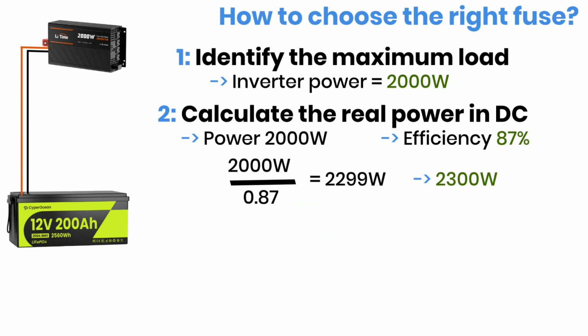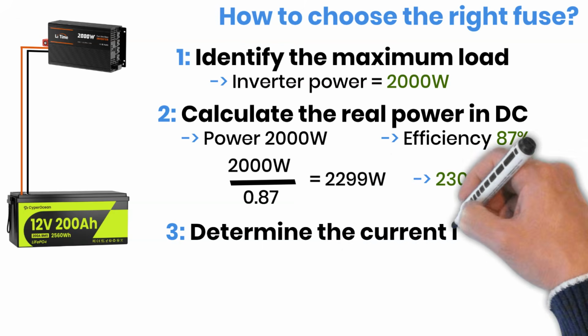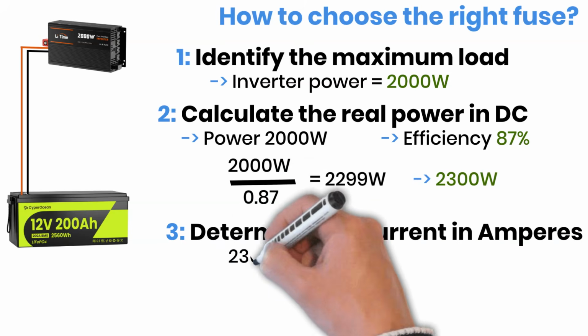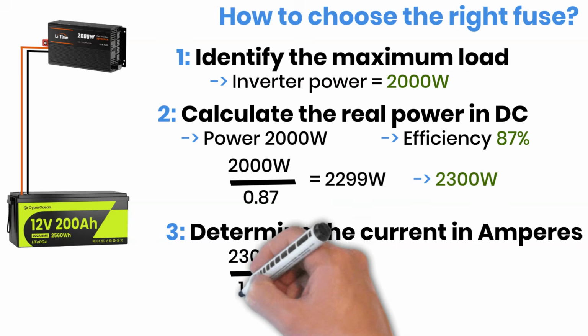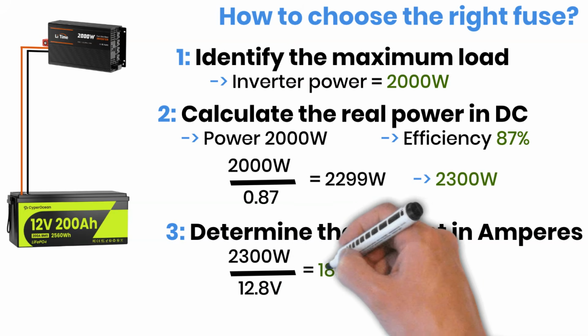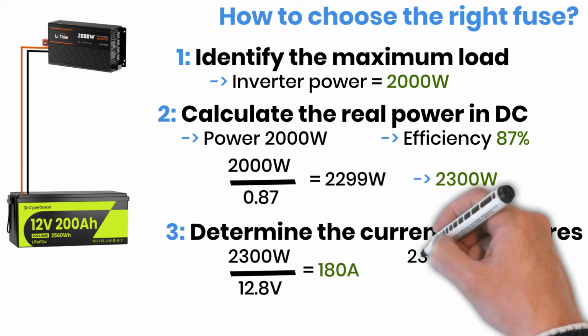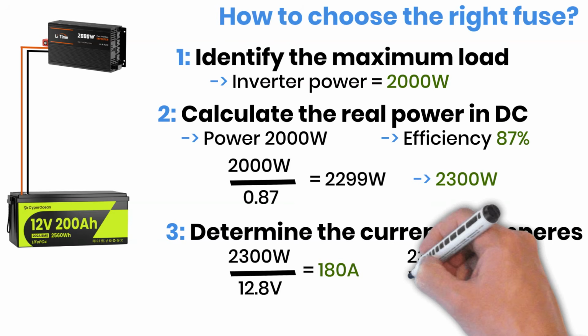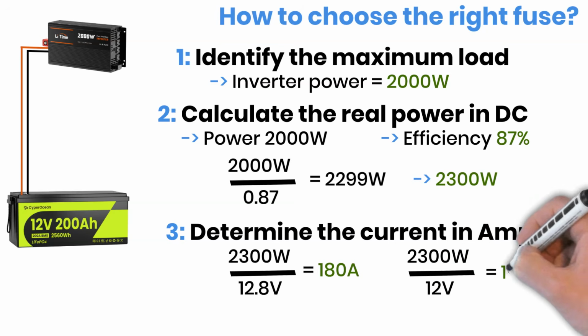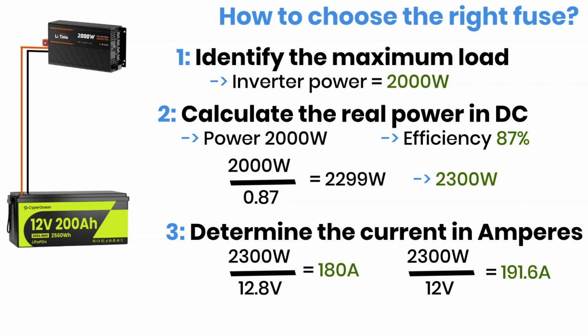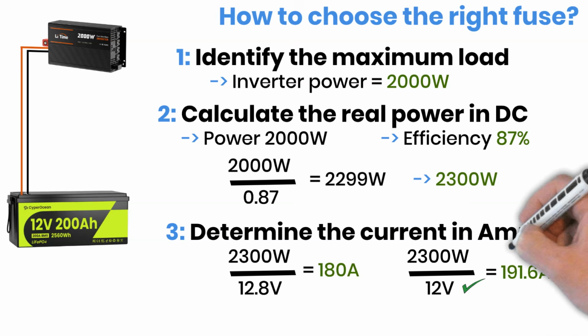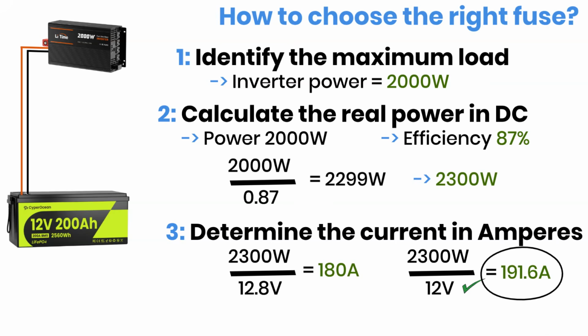Now we convert that power into amps. The formula is simple: power divided by voltage. So, 2,300 watts divided by 12 volts equals about 191 amps. You could also use 12.8 volts, but in real life, voltage drops under load, so using 12 volts gives a safer estimate. So now we know the inverter can pull roughly 190 amps from the battery at full load.